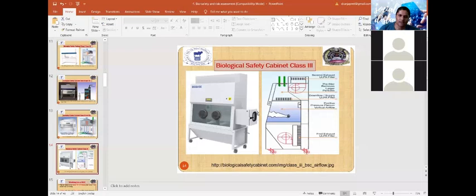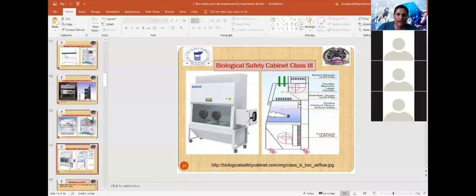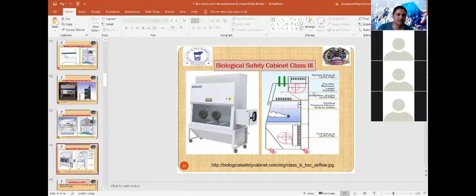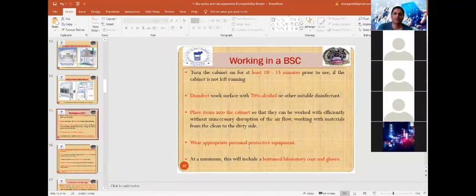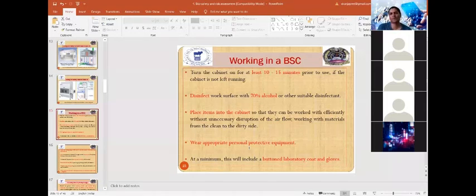In Class 3 cabinets, materials are introduced and removed through specific channels or outlets. After procedures, materials may be sterilized before removal. This ensures protection of the persons involved in the laboratory, protection of the product, and protection of the environment.